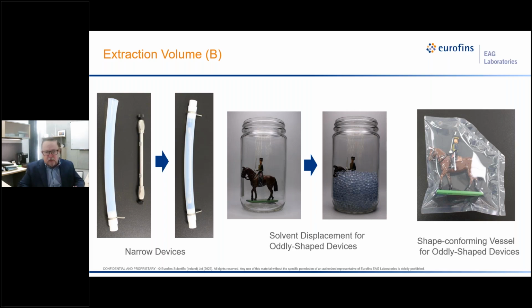It's really important that you use borosilicate glass so that you're contributing minimally to that extraction setup. But there are some other problems that can happen. For example, the glass beads can abrade the device, resulting in device degradation or contribution you wouldn't see under normal extraction conditions. The glass beads themselves can oftentimes contribute to the residue. They have coating, they can flake off glass. You will get a large silicon contribution in your ICP-MS data, for example, boron as well.